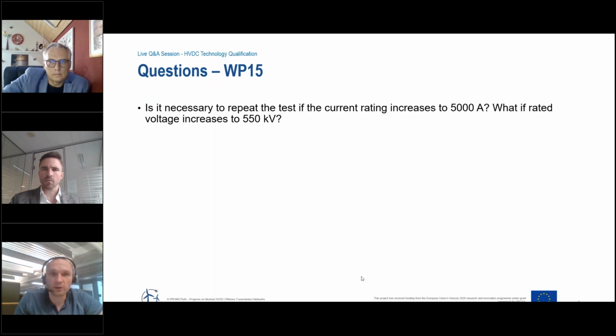When we increase the voltage rating from 350 to 550, for example, we would have a different geometry and newly designed solid insulators in the GIS. And in this case, the technical recommendation would be to repeat the test, because then we can have, let's say, a different balance of the different DC effects in the insulation, and then it would be advised to really repeat this test for the 550 design.